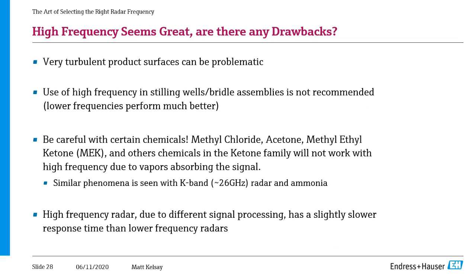The last point is that high frequency radar does have a slightly slower response time than lower frequency ranges. That's just because of a little bit of extra signal processing. So it's not a lot, but if you do have a small vessel that fills and empties very quickly, you're probably going to be better off with a lower frequency band. Okay.